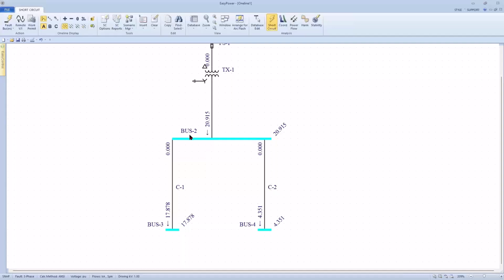Said, okay, this makes sense. If I have a fault here on the secondary of the transformer, each phase will see 20,915 amps. If I walk 50 feet away to this panel, each phase will see 17,878. If I walk 1,000 feet to this panel, each phase will see 4,351 amps.